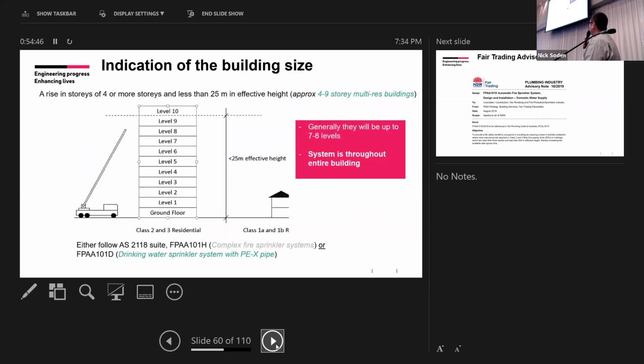So the building types: generally it's any buildings, class 2 or 3, above 4 floors or less than 25 metres in effective height, is where this system comes into play. And if it's a 6-storey building, it doesn't mean the sprinklers are only installed on the 4, 5 and 6 levels. It's actually from the ground floor up. Okay, so the system is through the entire building.